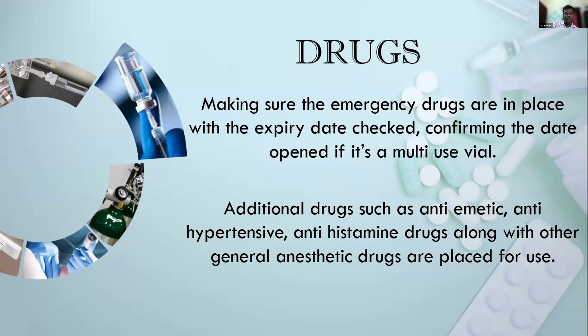Moving from the drugs, we move on to monitors and machines. We check whether the machine is fine from top to bottom, from the electrical circuits to the breathing systems. Before the anesthetist turns up in the theater, we make sure the breathing system is leak-free, and the breathing circuit matches the patient. If it's an adult patient, we use an adult circuit, and if it's a neonate, we downsize the breathing systems to neonate size.